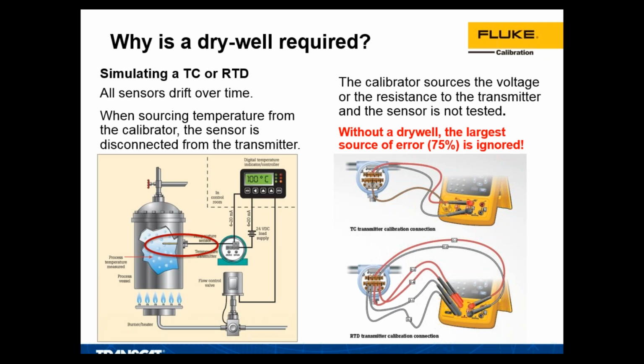But all sensors drift over time, and when you ignore the temperature sensor, you're actually ignoring the largest source of error. Rosemount estimates it to be about 75% of the error in a temperature measurement involving a temperature sensor and a transmitter. So what you see on the left is just an illustration of a process with a temperature sensor inside of a vessel, and then it's connected to a transmitter, a little green item there, and then that's being read by someone in a control room on a panel somewhere.